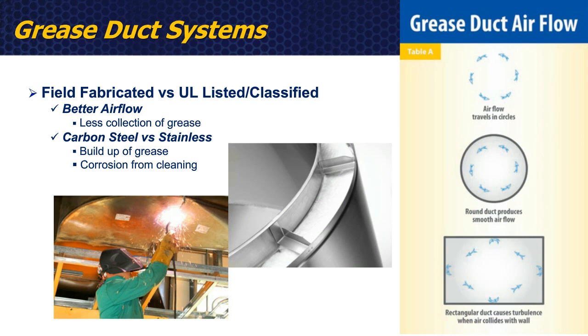There's also a significant risk of grease duct systems of buildup of grease inside of them that would present a fire risk. So if you look at the little chart on the right-hand side, air tends to flow in a circular pattern inside of a duct system, especially inside of a grease duct system. And by having a round duct and stainless steel construction, we have much better airflow on straight sections, transitions, and so forth, versus a rectangular ductwork, which is going to have straight sides and broken corners, which is going to have much greater risk for collection of grease in those corners, especially as I look at changes in directions. There's going to be a much greater risk of buildup and/or risk of leaving behind residue from when they clean the system.